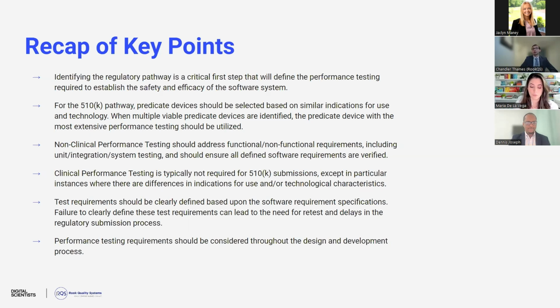And in part of bringing the device to market for the 510(k) pathway, definitely want to make sure that the predicate devices are selected based on similar indications for use and technology. When multiple viable predicate devices are identified, the predicate device with the most extensive performance testing, as well as the least amount of medical device reports and adverse events, recalls, corrections, removals, is going to be utilized.